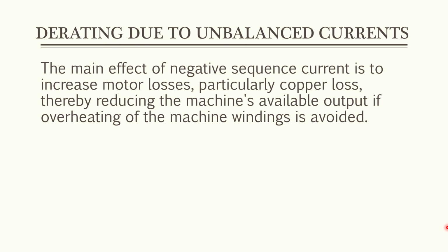So, when we introduce unbalanced current to the motor, we tend to increase the copper loss. And when the copper loss increases, the heat produced by the loss is increased as well. So as the copper loss increases, the temperature also increases, and thereby it overheats the machine. And hindi naman natin gusto na mag-overheat yung machine. So we tend to pull it off or cut it off out of the supply. Therefore, we cut the maximum output of the machines.